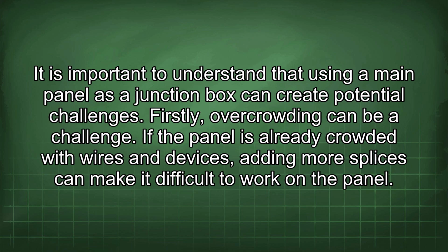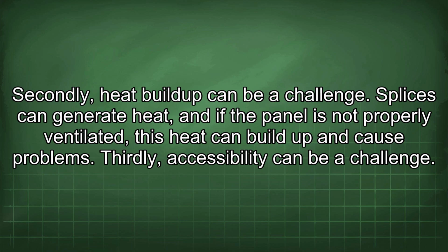It is important to understand that using a main panel as a junction box can create potential challenges. Firstly, overcrowding can be a challenge. If the panel is already crowded with wires and devices, adding more splices can make it difficult to work on the panel. Secondly, heat buildup can be a challenge. Splices can generate heat, and if the panel is not properly ventilated, this heat can build up and cause problems.